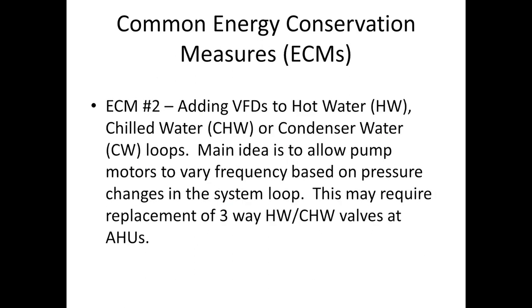We have ECM number two, which is just a generic adding VFDs when they make sense to hot water, chill water, or condenser water loops. Many times there's a lot of pumps and motors that are overworked when they don't need to be. So looking at if there's a way to reduce that fan or pump energy by installing VFDs and whether or not it's cost effective.